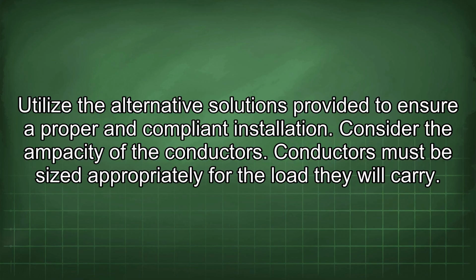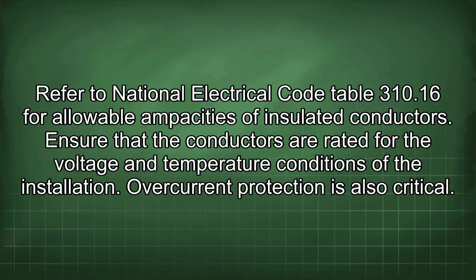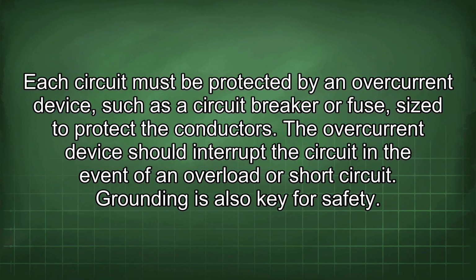Consider the ampacity of the conductors. Conductors must be sized appropriately for the load they will carry. Refer to National Electrical Code Table 310.16 for allowable ampacities of insulated conductors. Ensure that the conductors are rated for the voltage and temperature conditions of the installation. Overcurrent protection is also critical. Each circuit must be protected by an overcurrent device, such as a circuit breaker or fuse, sized to protect the conductors. The overcurrent device should interrupt the circuit in the event of an overload or short circuit.